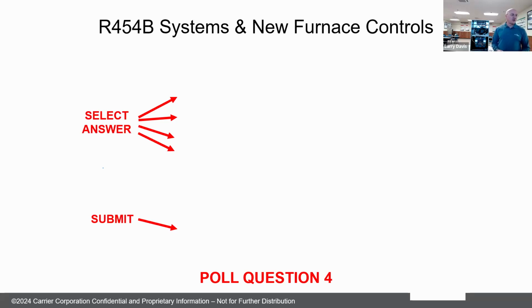All right. So question 4, what should be considered regarding A2L service items and tools? Make sure you have ventilation, and a leak detector that is adequate and A2L compatible. Service equipment, vacuum pumps, and so on are compatible. Gauge manifold and charging hoses dedicated for a 454B system, or all of the above. What's the best answer there that you see? I'll give it about a minute or so to answer this poll question. All right. A few more answering there. Give it a few seconds. All right. I think that's everybody. That's going to do.